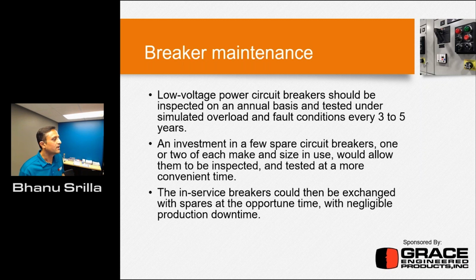Okay, so breaker maintenance. This is one of the major things that we come across. A low voltage power circuit breaker should be inspected on an annual basis, and the test should also be simulated under overload and fault conditions once every 3 to 5 years. The main reason is that it's not just a breaker sitting there; it's going to function when a fault occurs. You need to make sure the system will perform its designed function, like tripping. The breaker has to trip in case of fault or overload conditions. So how do you know it? You know it only if you test it, and the testing has to be done with reference to the manufacturer's guidelines and also the industry standards.